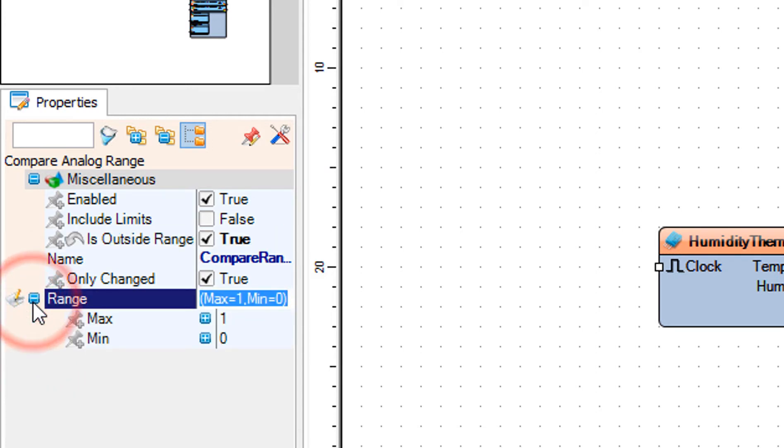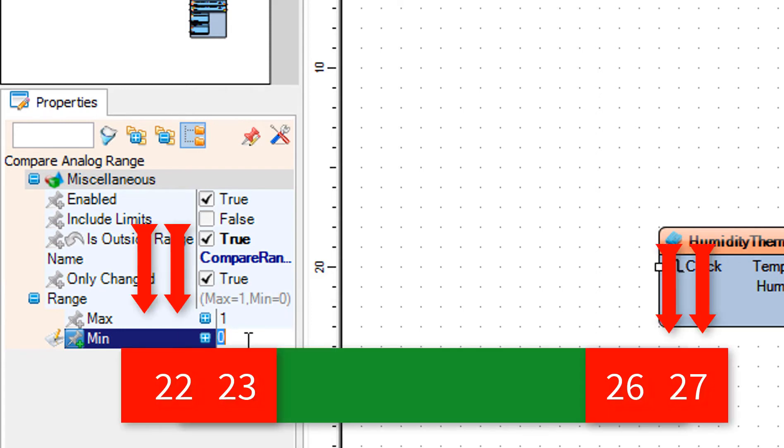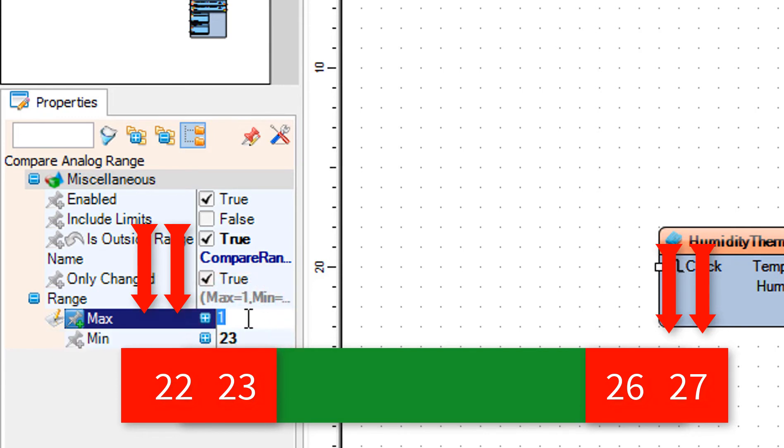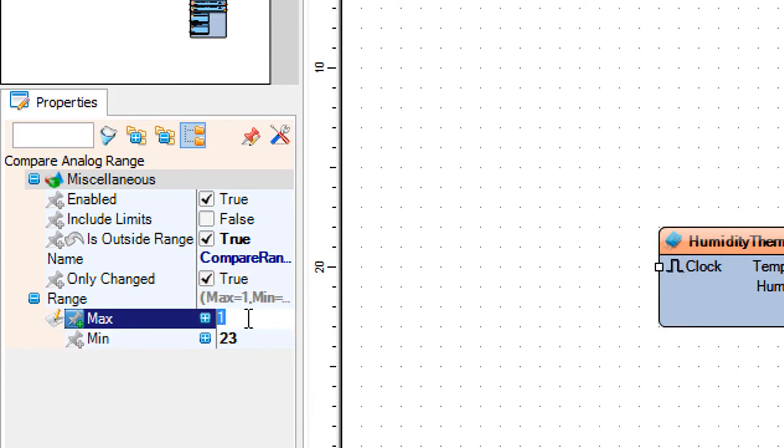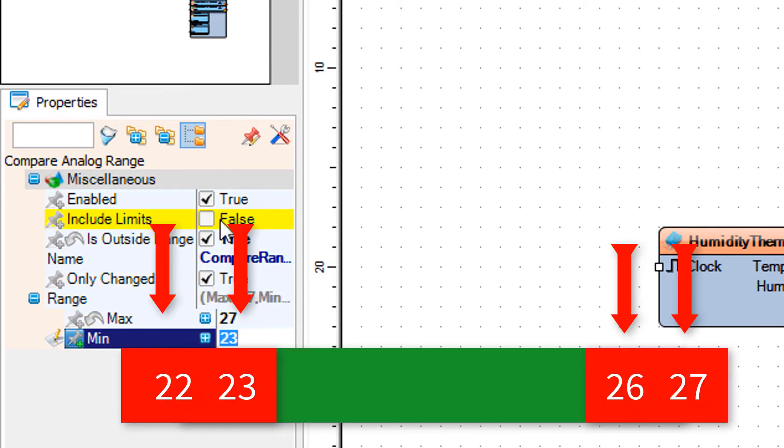Set range max to 26 and range min to 23. This means that the alarm will be triggered if the temperature is below 23 or above 26. Optionally, you can also set include limits to true. This means that the alarm will also be triggered at 23.